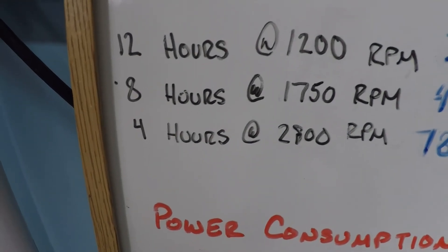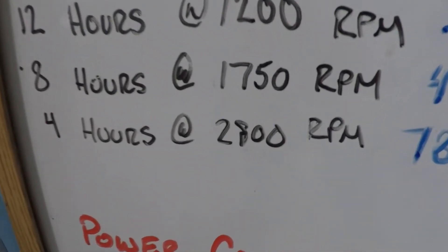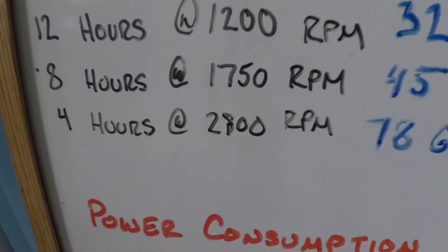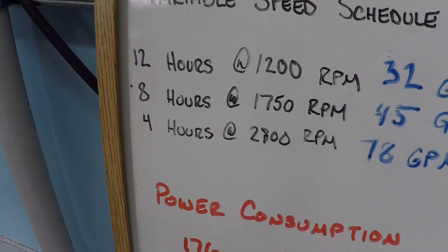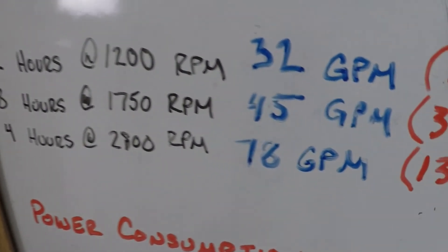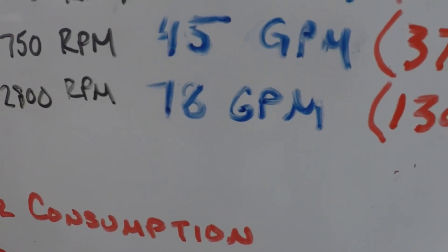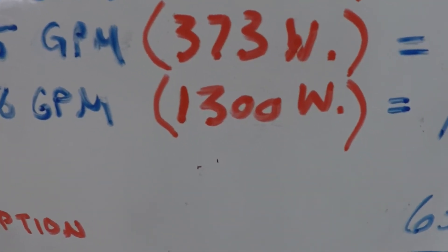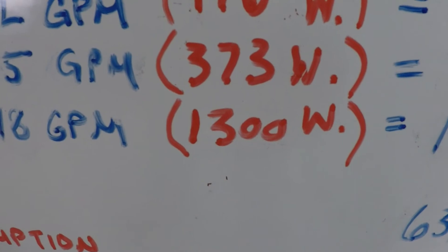But we also need a period of time at the higher speeds. Maybe not the highest speed because there's an advantage in dialing back just a little bit from the very maximum RPM. You'll only drop a few GPM but you will drop a fair portion of power consumption.